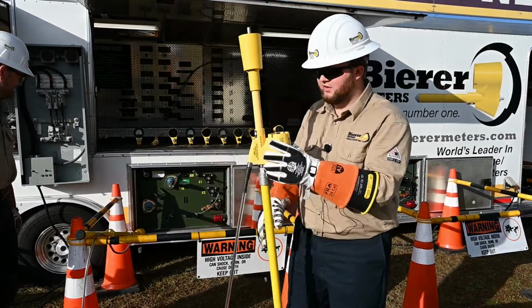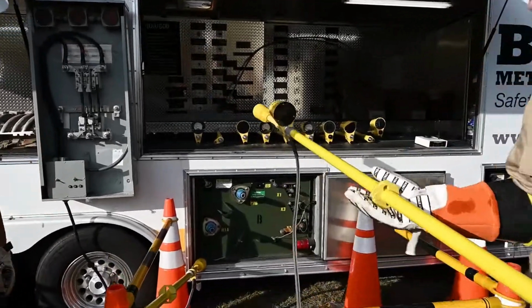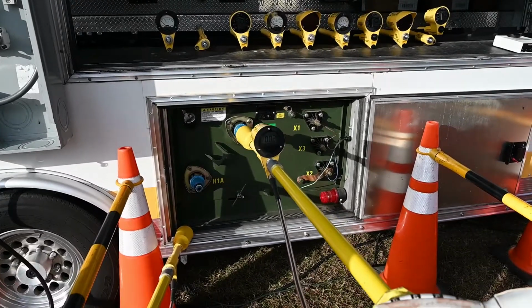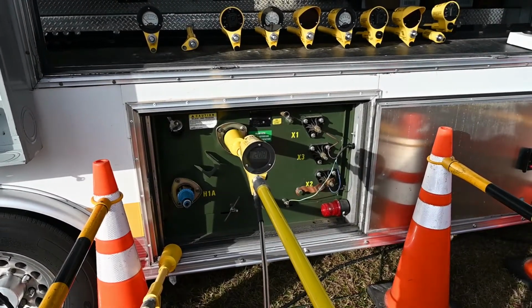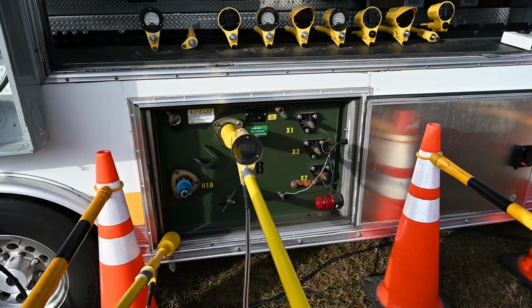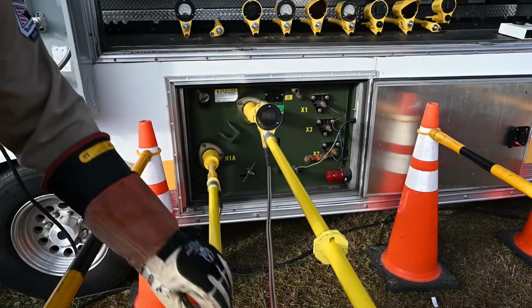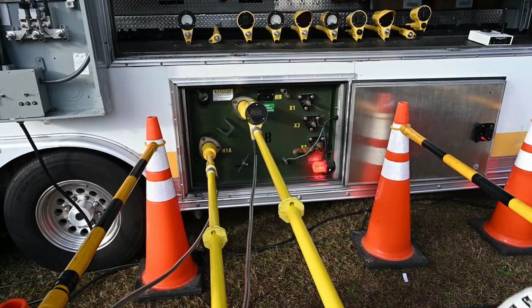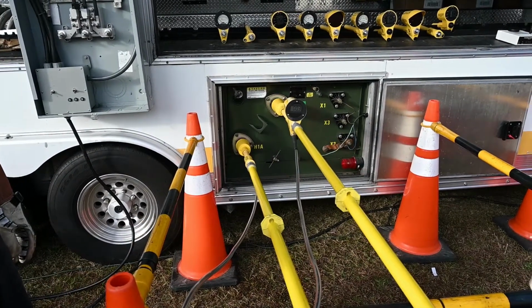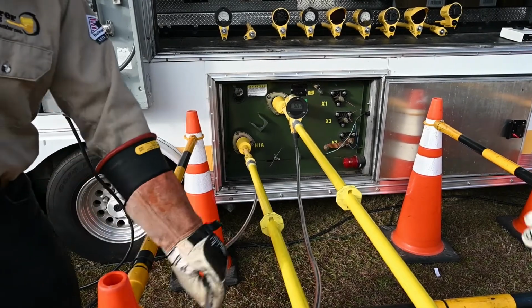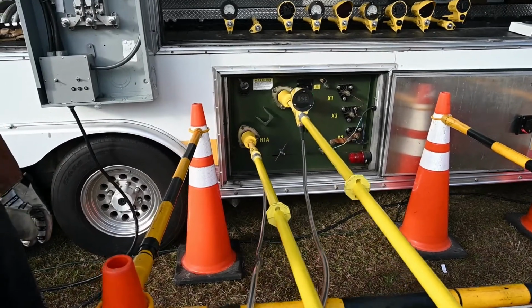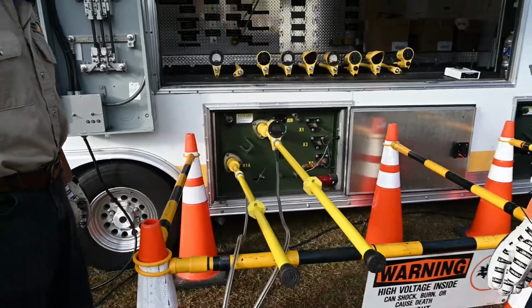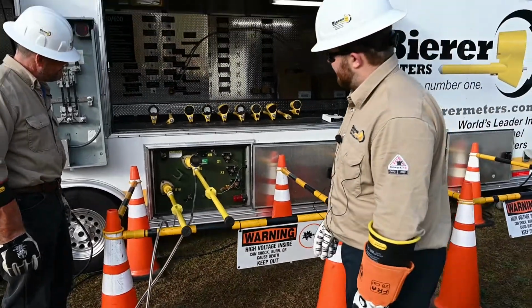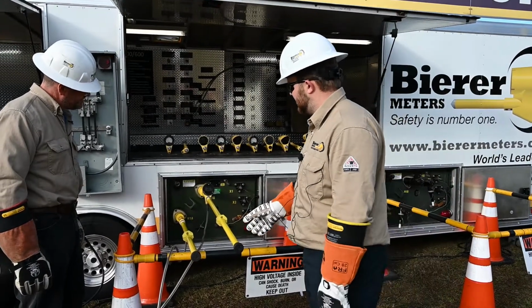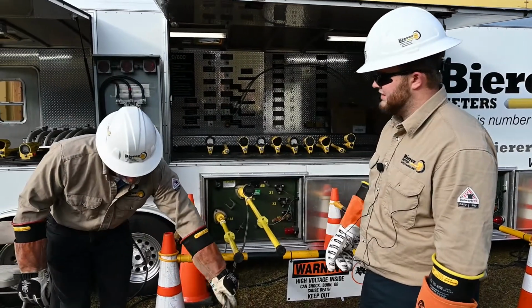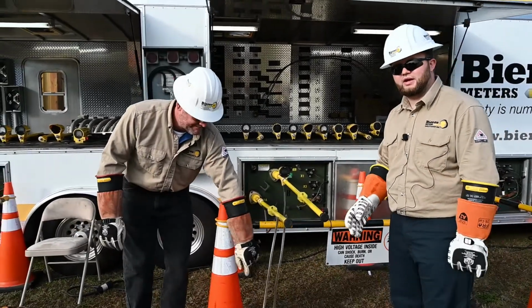So flipping to the 25 kV setting. Again, phase to ground. And we see about 20.6 kV. With this using our trailer as the ground, it's got a good ground reference. If the ground in the transformer was hooked up correctly, that's what we could have been seeing there with the wireless tools. But here we go, phase to phase. We're in phase. We don't quite see 0, we see 0.3. The reason for that is the cord's laying on wet grass.